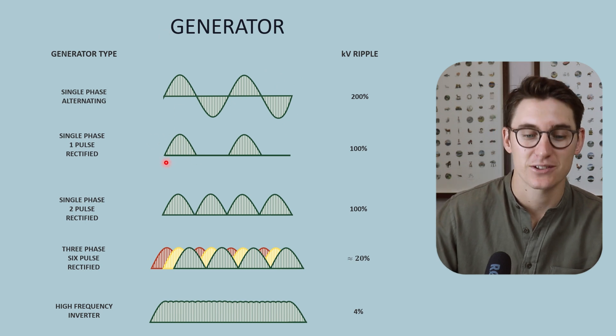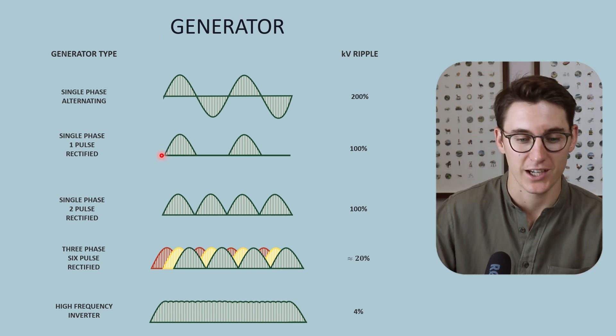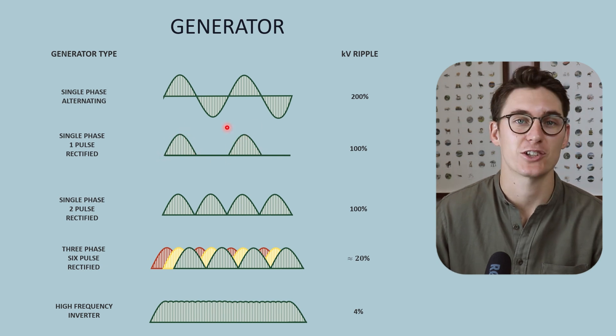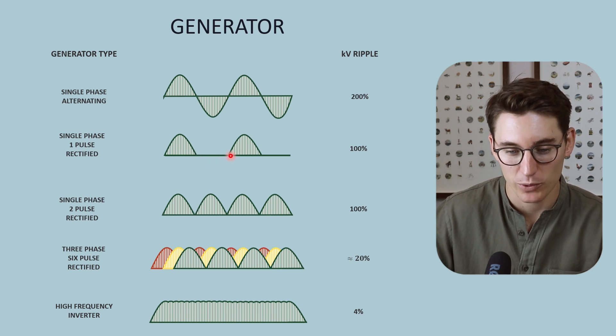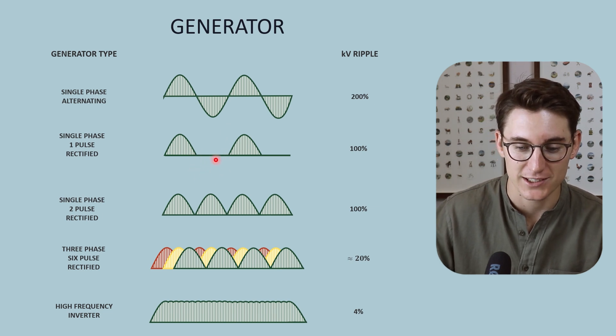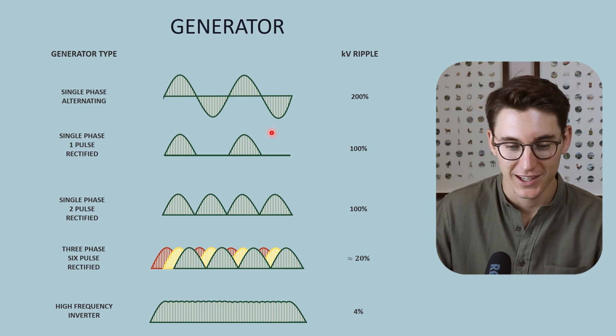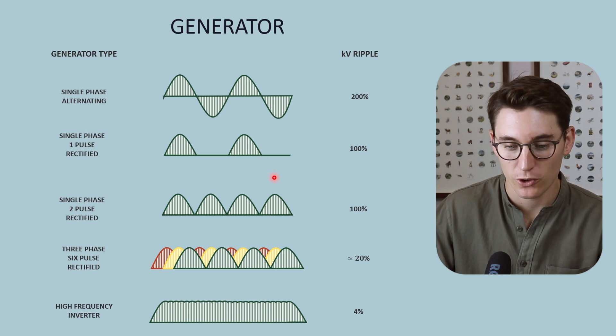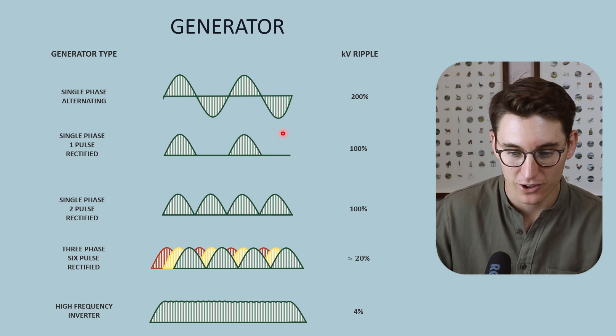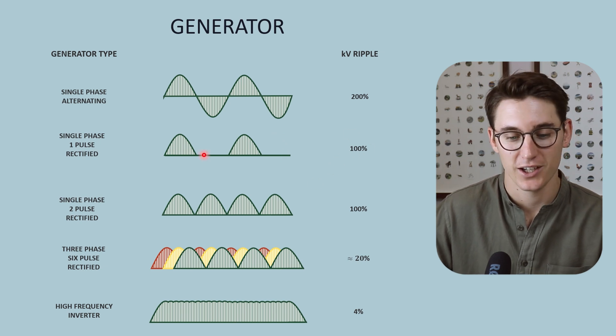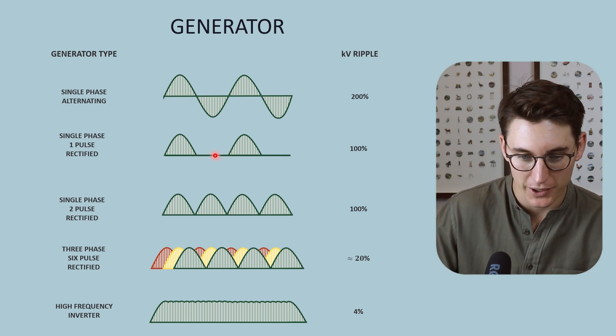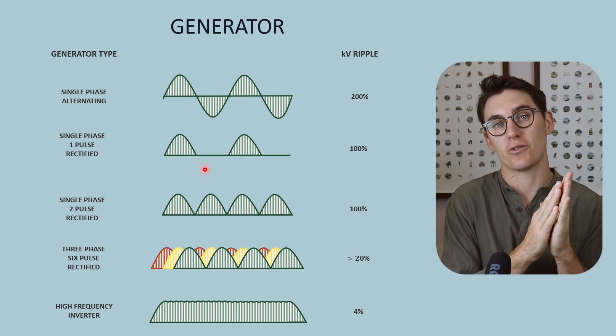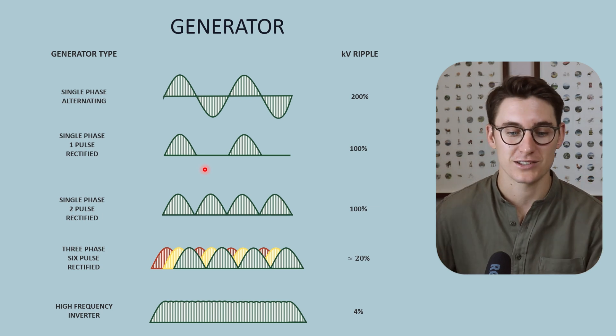If we look at half wave rectification, the positive deflections stay positive and we prevent the negative alternating current from passing through. The voltage peaks are the same as our single phase alternating current, but we no longer have that negative deflection — our KV ripple here is 100%. The issue is we have long periods of no voltage and no current flow, with no electrons going from our cathode to our anode for half of our cycle.